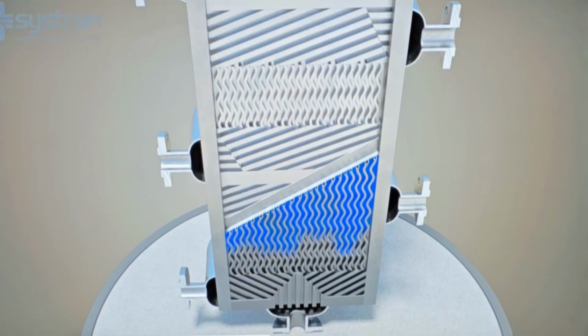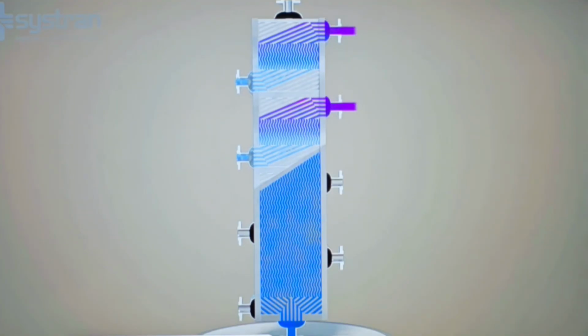As the feed gas flows down the exchanger, it is further cooled until it achieves the desired temperature for liquefaction. The resulting cold feed gas vapor exits the exchanger and flows to a JT valve, where it changes to a liquid. The hotter vaporized refrigerant exits the hot outlet to be returned to the...